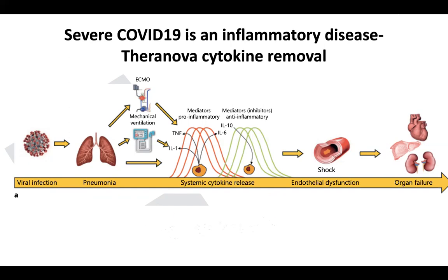There's some temptation to ask: could we take out some of these pro-inflammatory mediators? Can we remove cytokines? Cytokine removal has been tried for a long time. You can try with standard Prisma using high-volume exchanges, but the filters are not well designed to remove cytokines and the total amount removable is limited. You can't do it with standard hemodialysis because our standard filters cut off at about 20 kilodaltons, which is smaller than IL-6 and many other things we want to take out. Specific adsorption cartridges like CytoSorb have limited capacity, fill up quickly, are very expensive, and are not currently available in Canada.